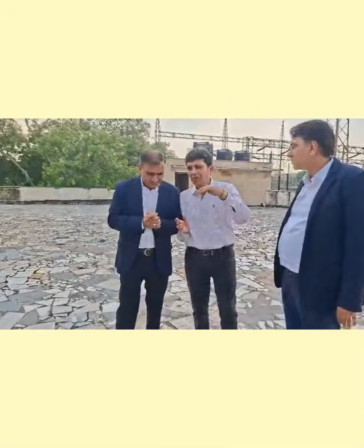Confirmatory. What about the interpretation of the other gases? Definitely, associated with the hydrogen family. How do you do that? Whenever we install the sensors on the transformer, on the same day we collect the oil samples also and test them in the lab, and that is treated as a reference value for the gas formation. Now, based on that, I can apply the Duval triangles, pentagons, Rogers ratio. But that is basically a tentative interpretation. That may be okay or not. Definitely, so that's why real-time tracking and lab testing are mandatory. So real-time gas tracking is with the hydrogen, and the rest of the gases are estimated based on their presence on day one.